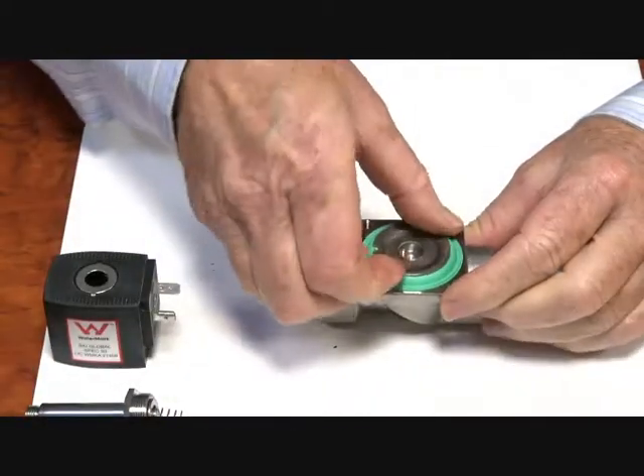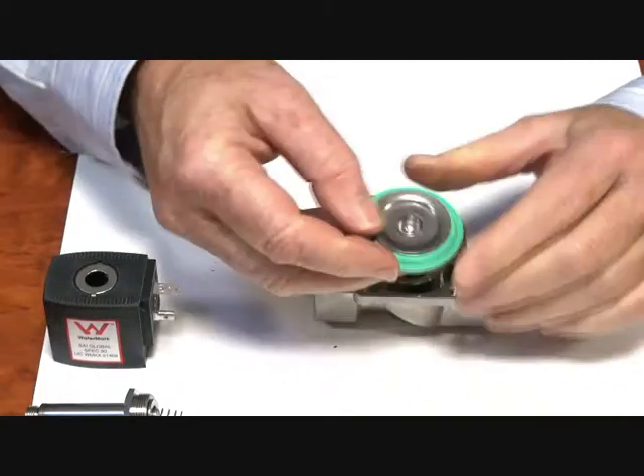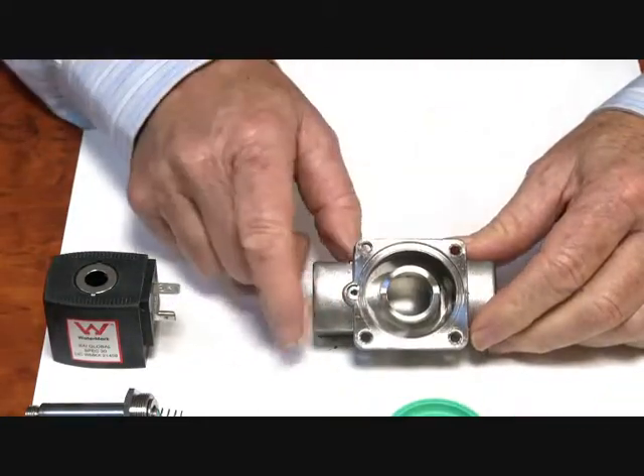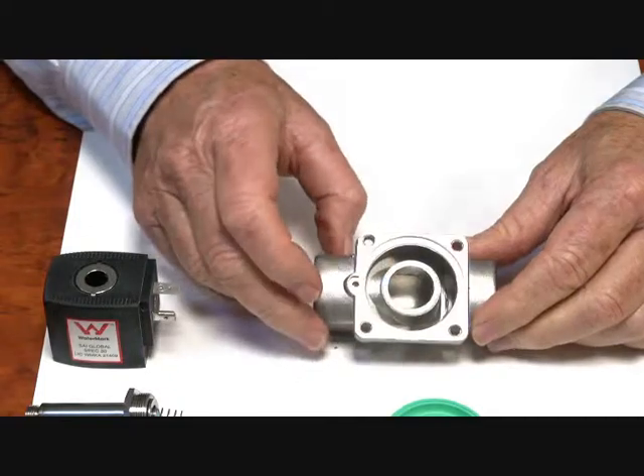Spring comes off. Diaphragm comes out. There's a little bleed hole there which must be kept clean. Diaphragm assembly and the jet seating assembly inside here.